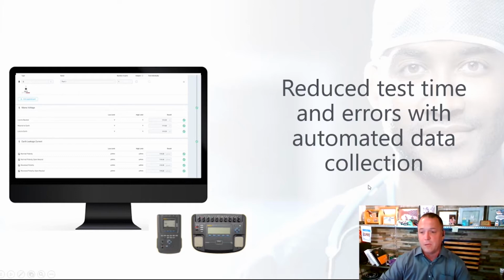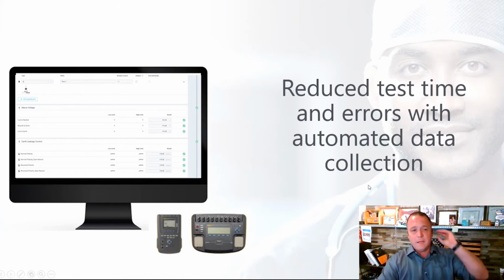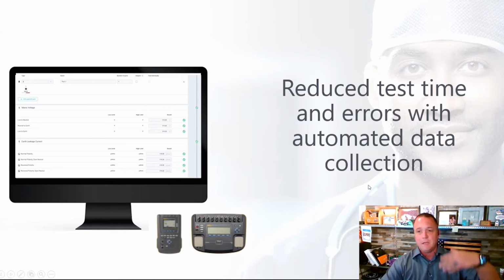Maybe they will have to pull it out of service or initiate that repair. So if it's 5.01, the result is 5.01, and not accidentally penciled to 4.99 so that it could be done with that device and moving on. That's going to save a lot of time, hassle, and heartache in the long run, because if you can mark an item or find the item at the onset of when it's failing and take care of the issue, that's usually a smaller issue than if it's on the backside and you have a patient incident that results because you left that piece on the floor and being used.